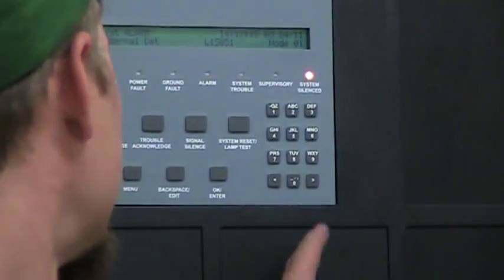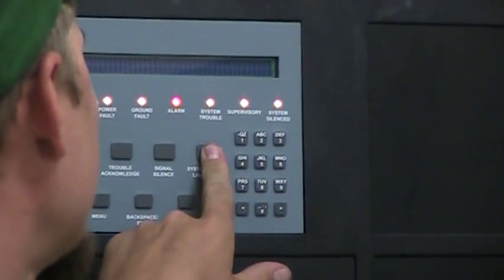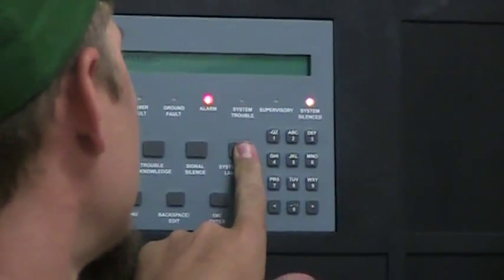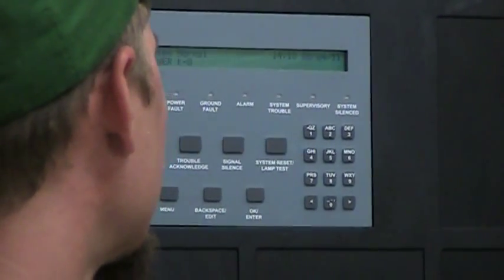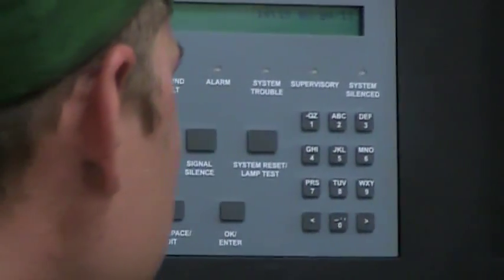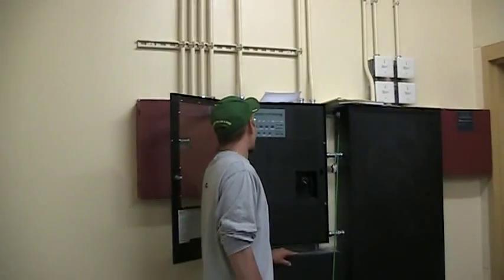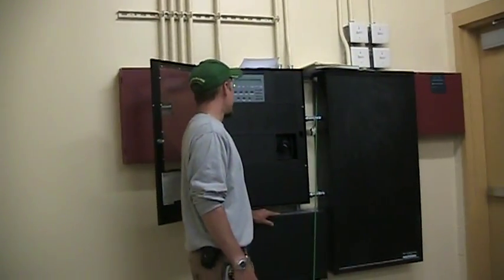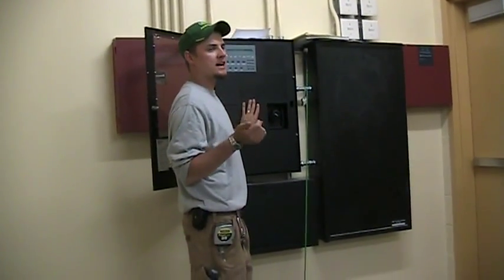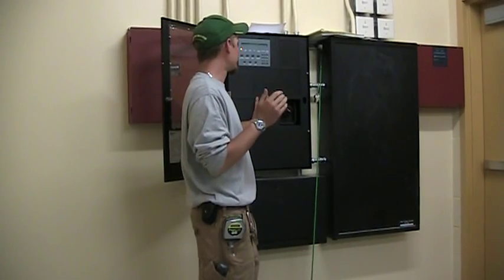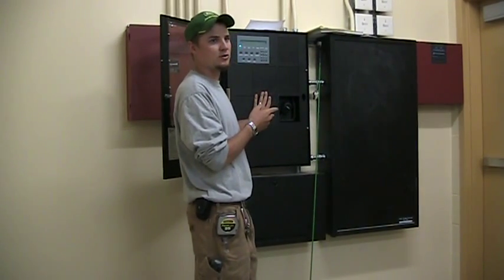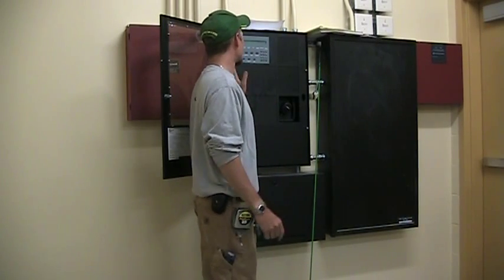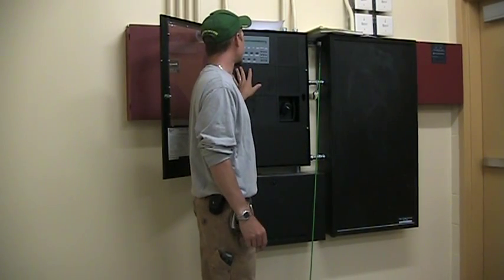Now, no one from the school should be resetting it. The only person that should be resetting it is Chris with the fire department. The system reset, we hold on. Now it's reset. And we'll give it a couple minutes and we'll come back up to speed. Any of these functions can be done from this cabinet or the remote mic cabinet down by the auditorium. You can silence and reset from the annunciator at the front door, but any other things with the menu can only be done from this and the remote mic cabinet.